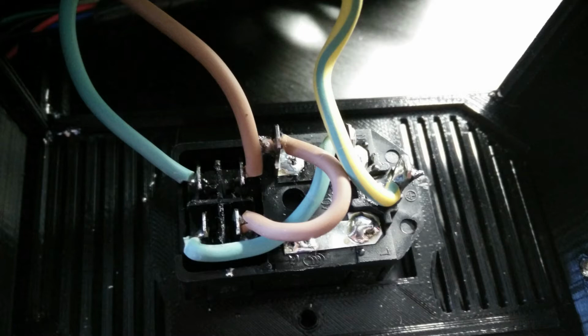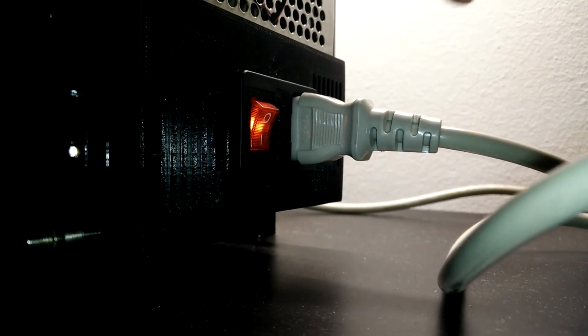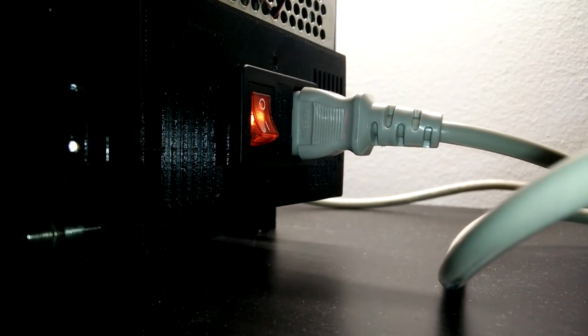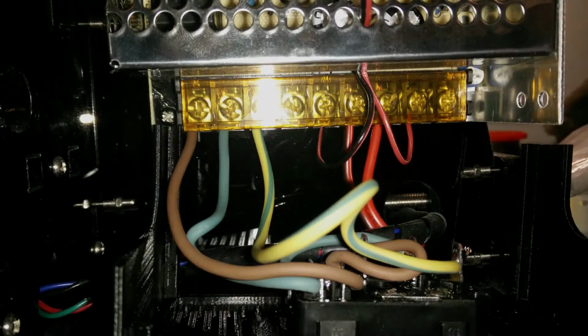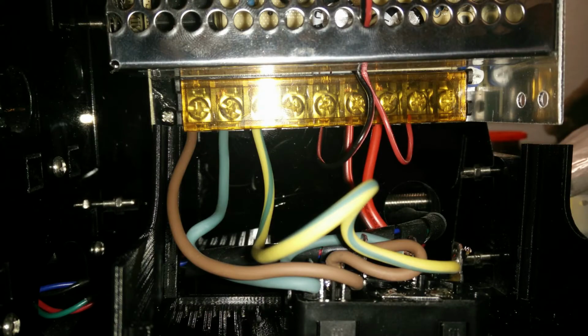Something I had to find out the very hard way is the side where the neon lamp has its connections to. The small lamp should only light when the switch is on. In addition to that, the color code should be taken into account. Green-yellow stands for the protection earth, blue the neutral, and brown or black the hot wire.